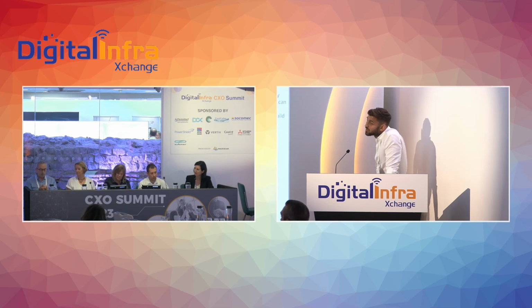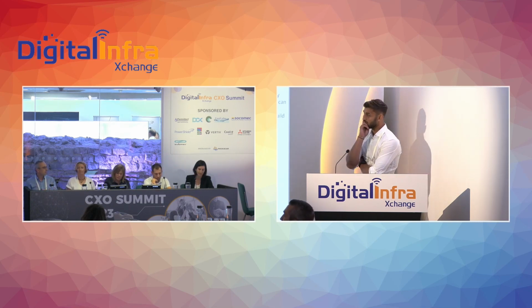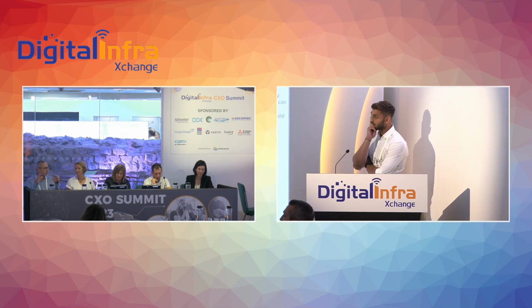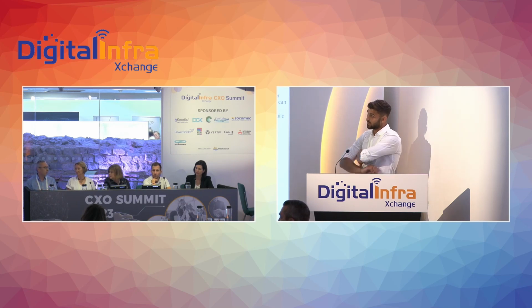The second point is about power saving, battery charging, these kinds of things, or UPS. I've been in UPS for a long time. I go to every site and the UPS are charged at what, 30%? And people say, oh, we need the big design, we need to be careful. But if you reduce the power usage by your IT, you reduce the UPS, and it all cascades down and reduces the consumption. So focus a bit more on equipment, and it will be good.